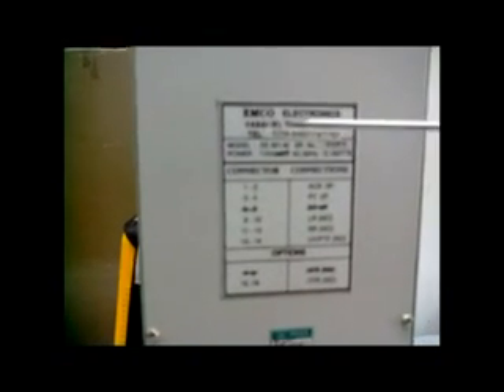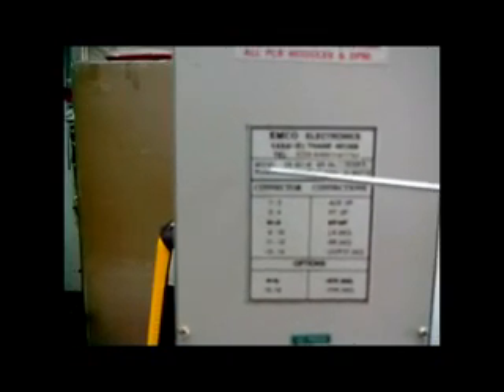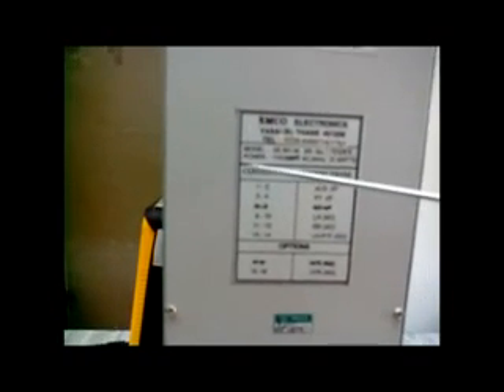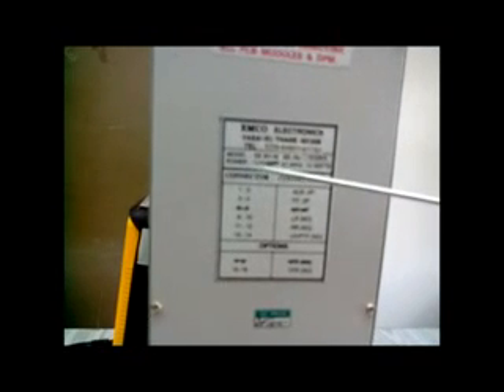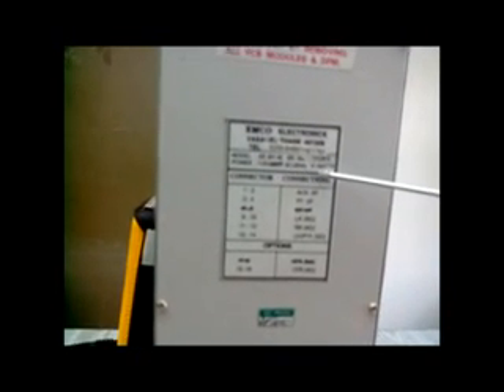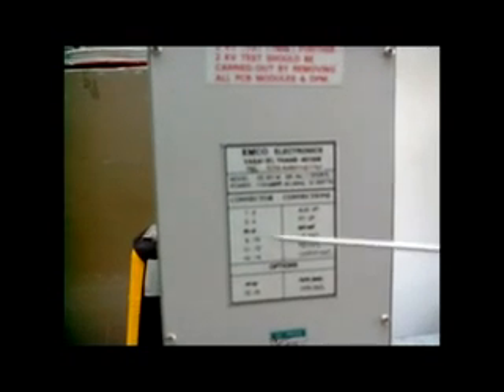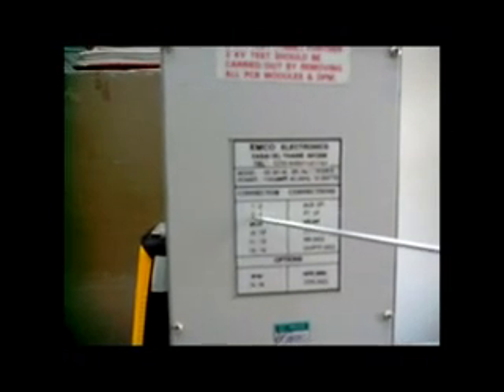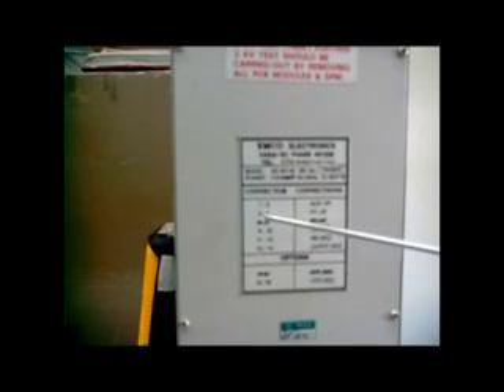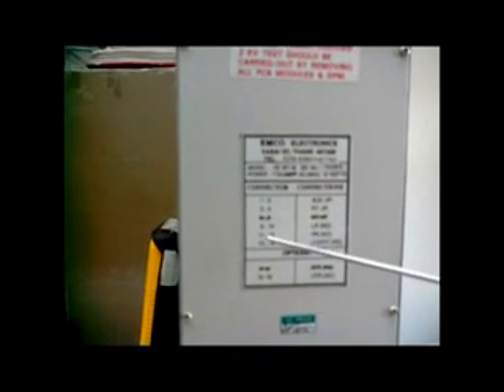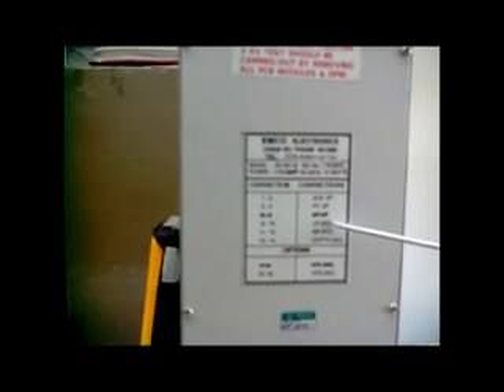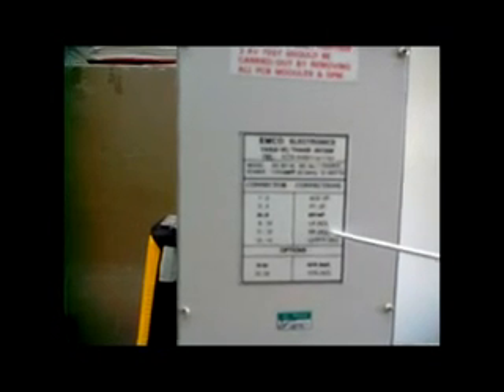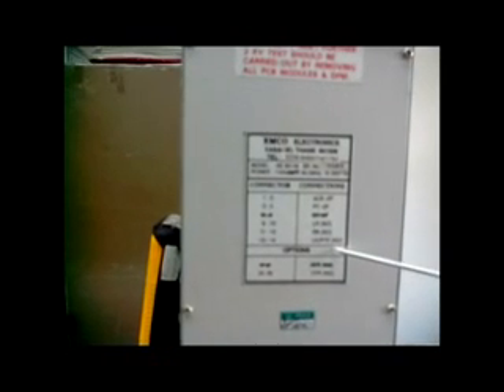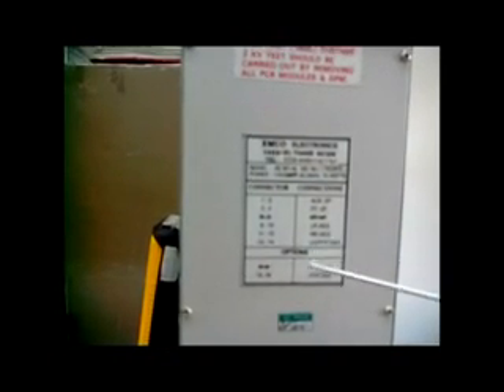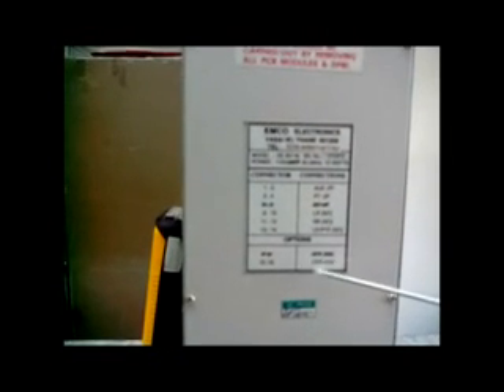This is the rear panel of the regulating relay. There is a terminal station for connection, and the details of terminals are provided on the rear panel nameplate. On the nameplate, auxiliary supply voltage and burden are mentioned. It also describes the pin numbers of the terminal station for the necessary circuits. Pin numbers 1 and 2 are auxiliary input, 3 and 4 for PT connection, 9 and 10 for LR, and 11 and 12 for RR, 13-14 for UV, and 15-16 for optional contacts.